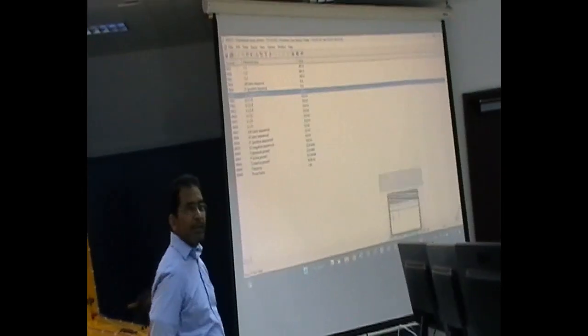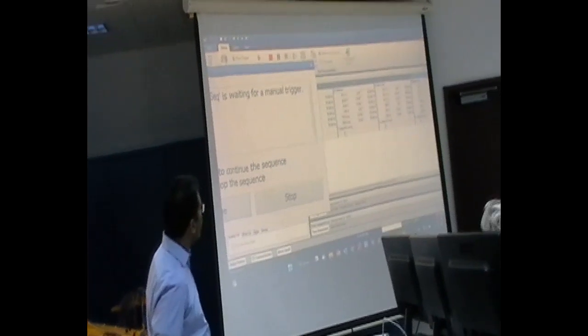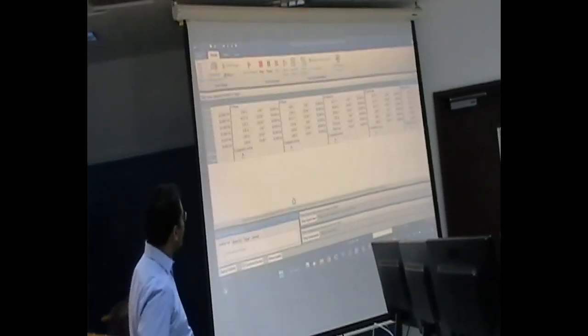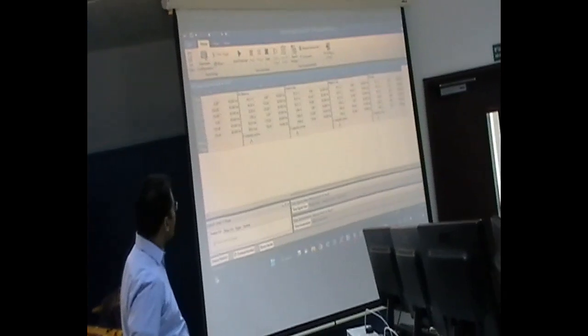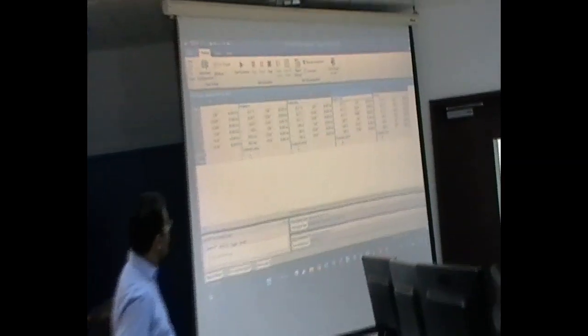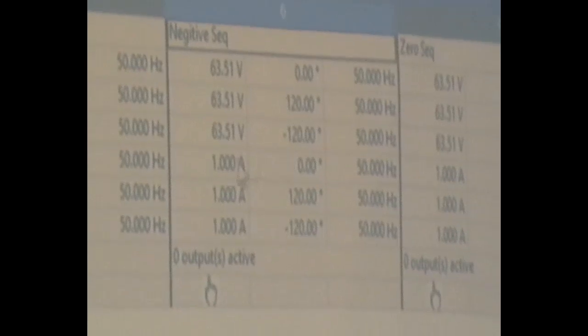I'll go through the injected values, then zero sequence once the test is finished. Otherwise, now I have to start the injection. Okay, we are here. This is the negative sequence. What we changed from here is only the angle. It was minus 120, now it's 120. And the same goes for the blue phase. It was 120, now it's minus 120. The same for the current also. We've reversed it only.